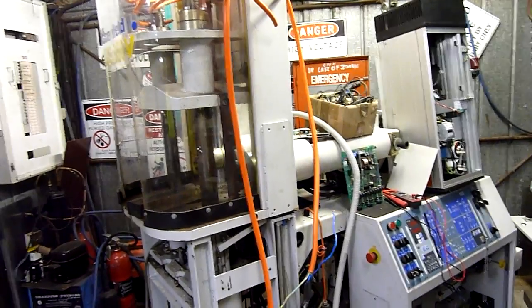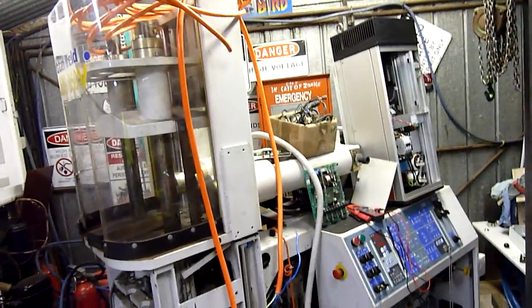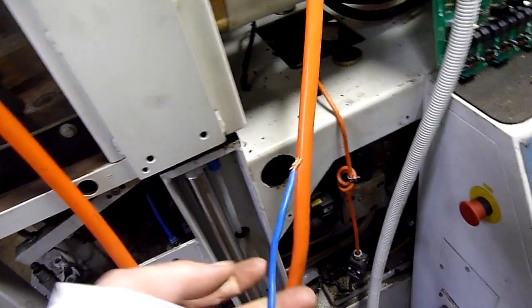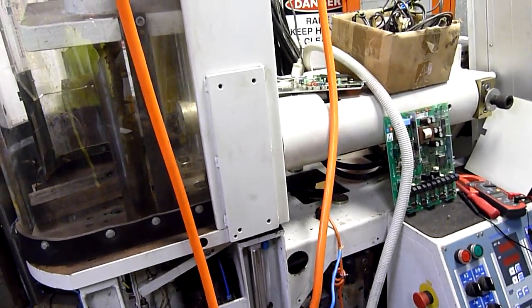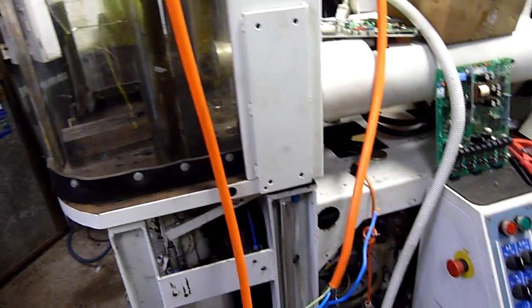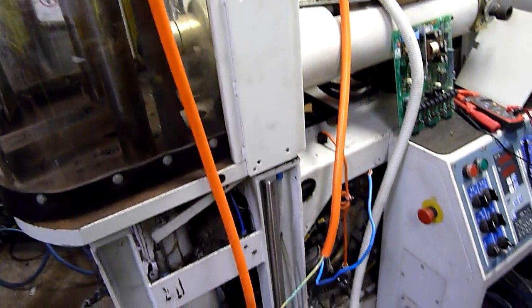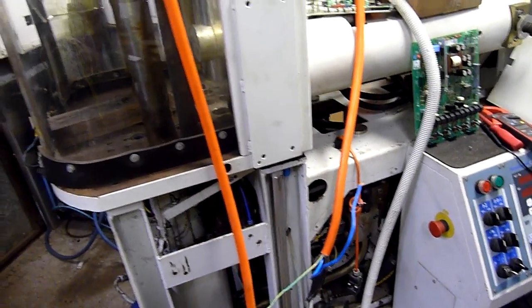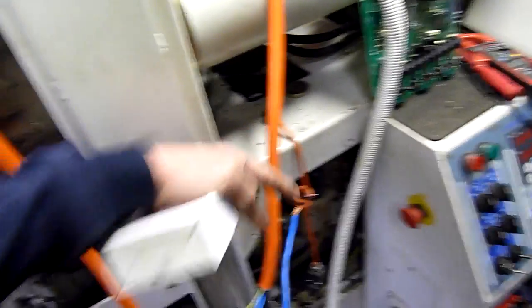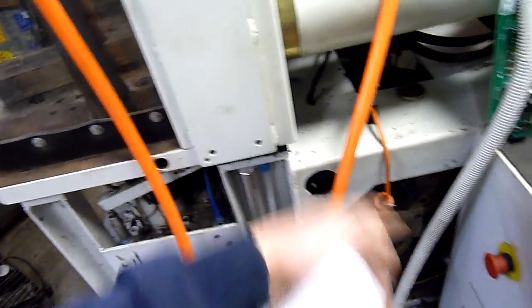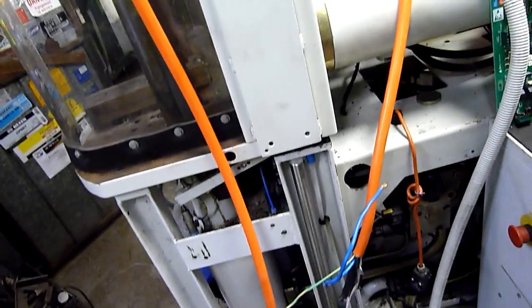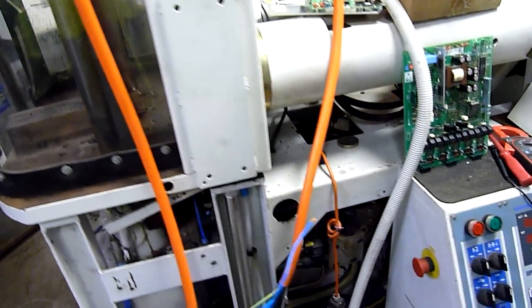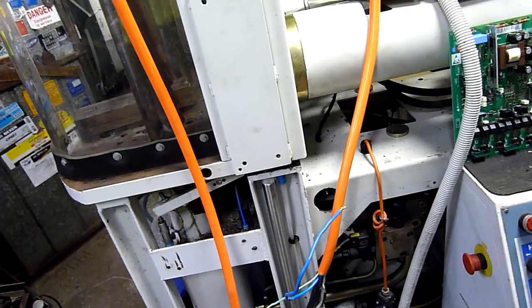The main concern is the feeder from the smart meter to the main RCD, the safety switch that distributes power to everything else. It's probably thinner than six millimeter square at the most. It looks thinner than that. It's lagged in cloth black cloth tape, so it's probably original from the 1960s. I'm thinking I might even pull the main house fuse on the fascia board and just see what it's like. It just goes into a double screw terminator and then splices off to six millimeter cable. The wire after it's rated properly, but the wire at the meter is not, at least not for an 80 amp service. At the moment it's only 40 amps.